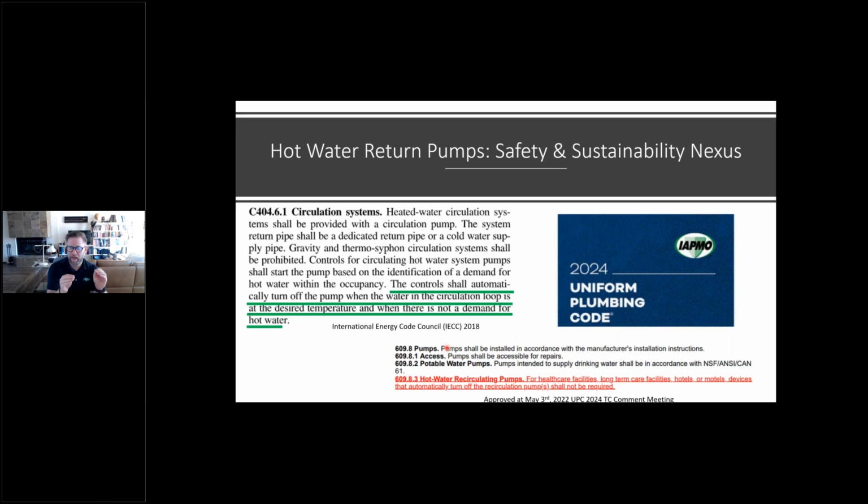And it stays permanently in a tepid or tempered system, basically between, let's say, 90 to 120 degrees. Well, unfortunately, that's a growth range for waterborne pathogens, especially Legionella pneumophila, which we know loves about 100 degrees Fahrenheit plus or minus 20 degrees Fahrenheit. And now, in essence, you created a situation by turning that recirculation pump on and off, to try either to meet code or to prevent temperature creep, of having a location where that pathogen is growing, because in essence you have a slug of water that's not getting moved, especially if the system is unbalanced. So we've compounded an issue by trying to solve another issue, and that's where plumbing resiliency really comes in. You have to think through problems holistically.